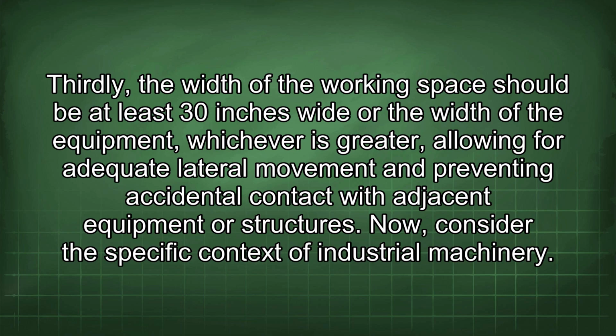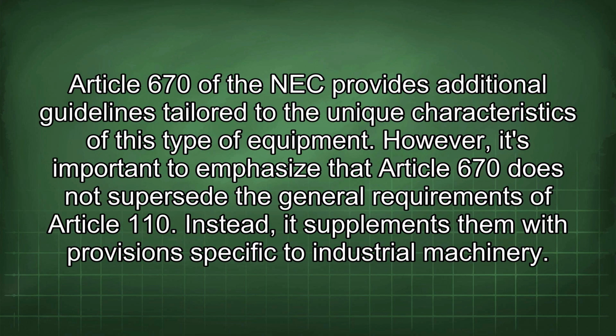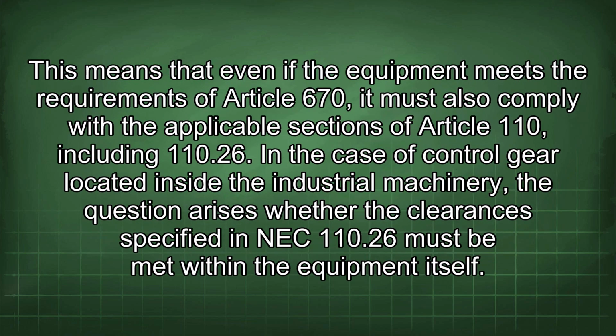Now consider the specific context of industrial machinery. Article 670 of the NEC provides additional guidelines tailored to the unique characteristics of this type of equipment. However, it's important to emphasize that Article 670 does not supersede the general requirements of Article 110. Instead, it supplements them with provisions specific to industrial machinery. This means that even if the equipment meets the requirements of Article 670, it must also comply with the applicable sections of Article 110, including 110.26.